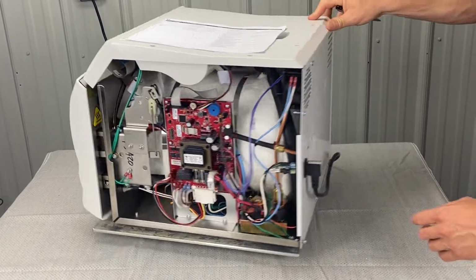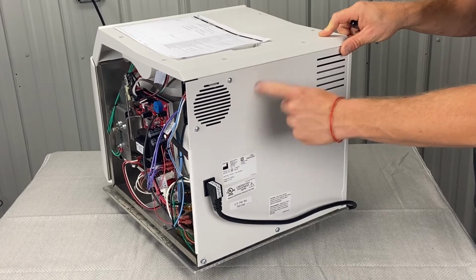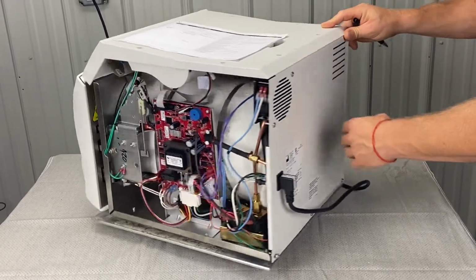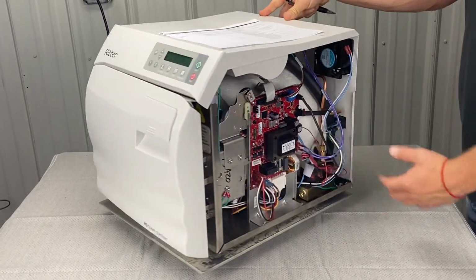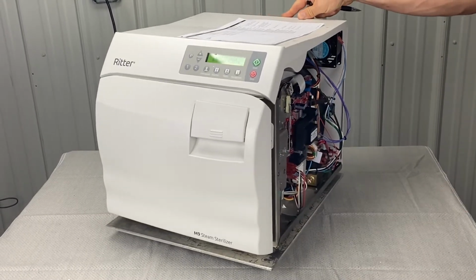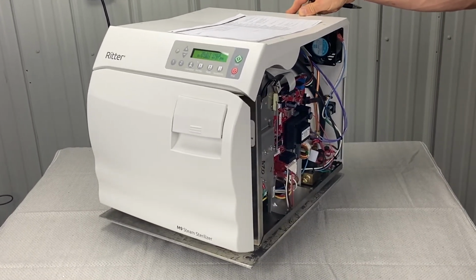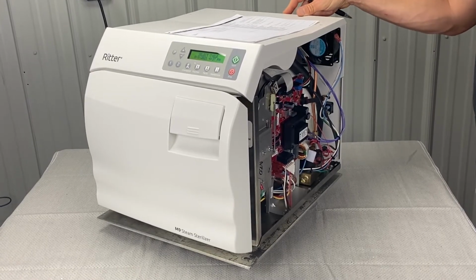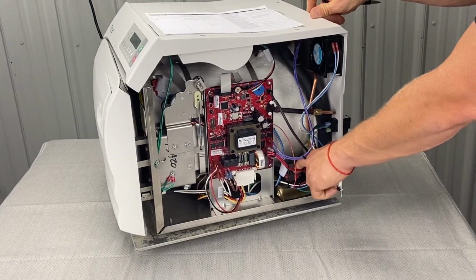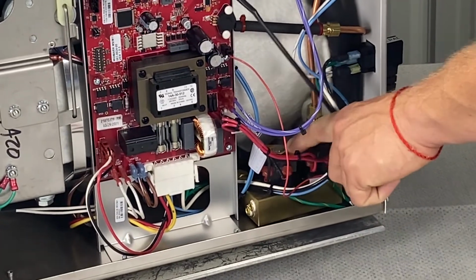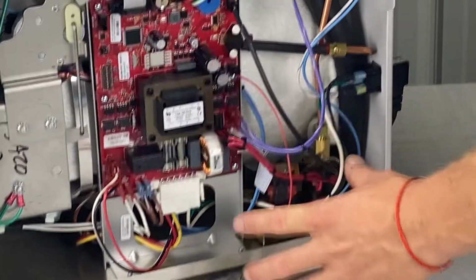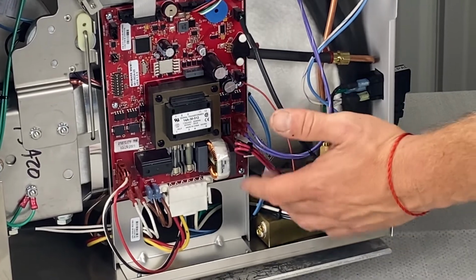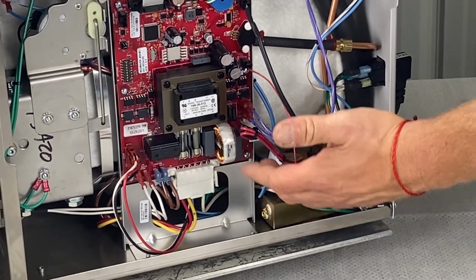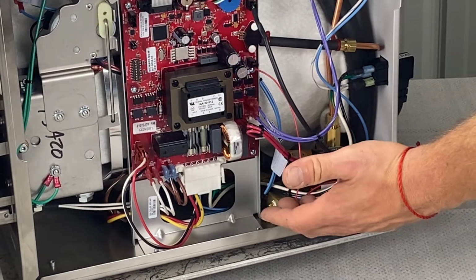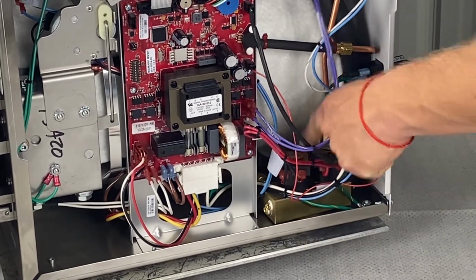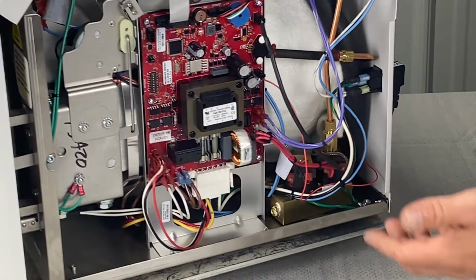Also, there's an air vent bellows in the back here. There's another valve right here that purges the chamber as the unit heats up and boils the water. That could be failing. So it could be any number of different areas. There are rectifiers on these. These are brand new, so they don't have them, but there are past models that did have the rectifier. Basically, if we determine that the rectifier is bad, you can buy that, or you could just buy the newer version, which has a built-in rectifier inside of it.